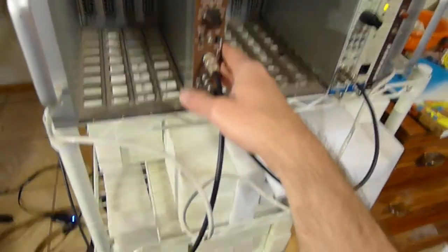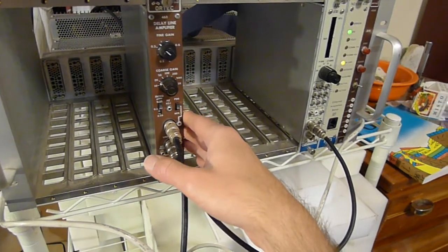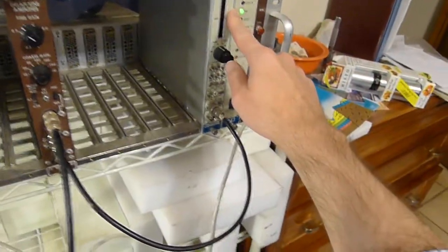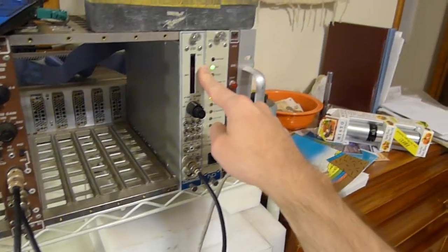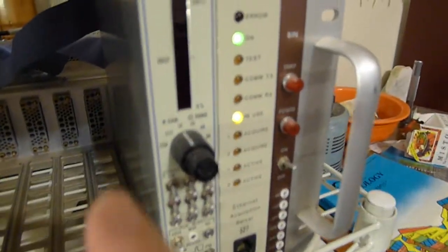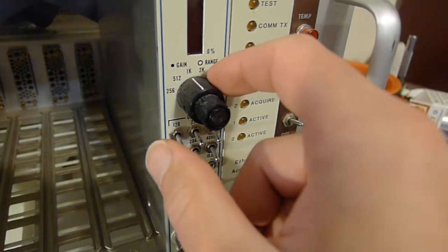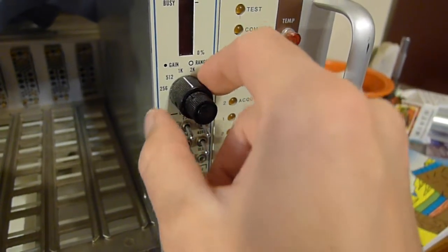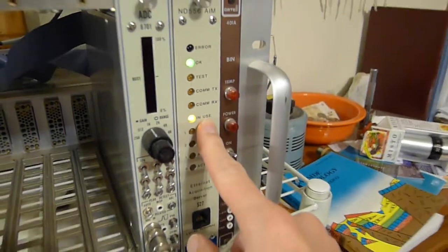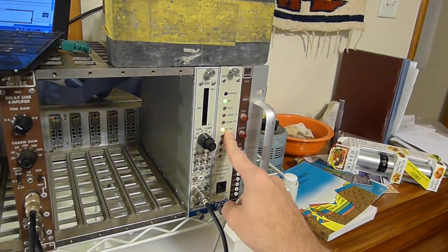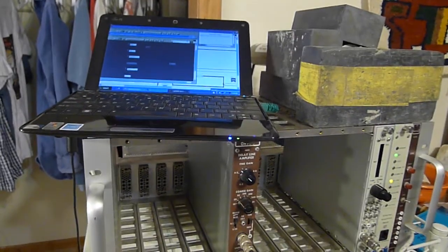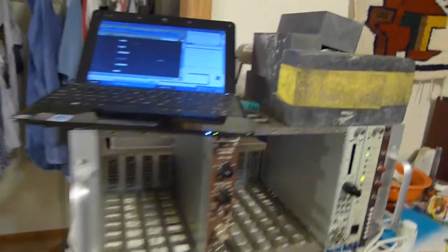That's followed in the signal chain by a shaping amplifier. This is a delay line amplifier. It's very typical for scintillation spectroscopy applications. Then there's the analog to digital converter. This takes the signal from the amplifier and turns it into a digitized signal, in this case divided into a span of 1,024 channels. And then finally we have the MCA, which is essentially memory that can be accessed by the ADC and also by the computer that can interpret the spectra that are acquired into the MCA. So anyway, that's the hardware.